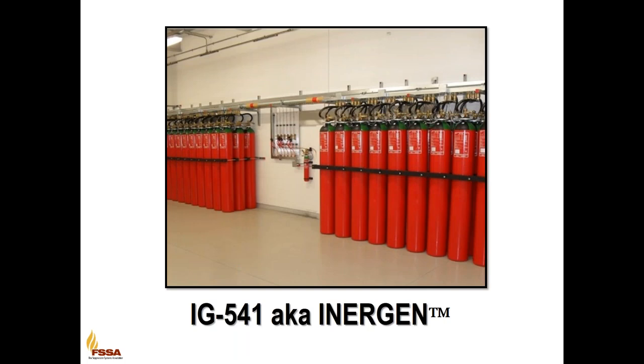Moving on to the inert gases, IG541, or Inergen, is an inert gas comprised of 52% nitrogen, 40% argon, and 8% CO2, components that are naturally present in the atmosphere. Therefore, its greenhouse effect is nil, and its ozone depletion potential is zero. It's chemically inert, non-conductive, colorless, odorless, and flavorless. IG541, or Inergen, is non-corrosive and may be used at normal temperatures with such materials as nickel, steel, stainless steel, copper, brass, bronze, and plastics.